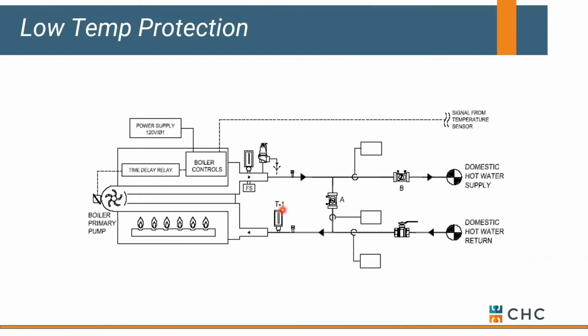Let's talk about how we might protect a non-condensing boiler. So if you've got a boiler that has a minimum return of 130 degrees, but you're bringing some colder water to it, how do you protect it? Well, this is one option. Now this works better as a water heater than it does as a boiler. So, but bear with me a second. If we're pulling out of a storage tank, we might have 90-degree water coming to this. I'm going to call it a boiler, but in reality, it'd be a water heater. Okay, let's just say 90-degree water.